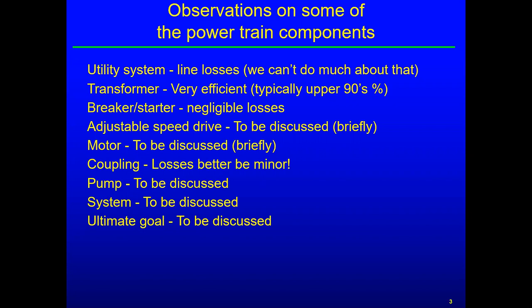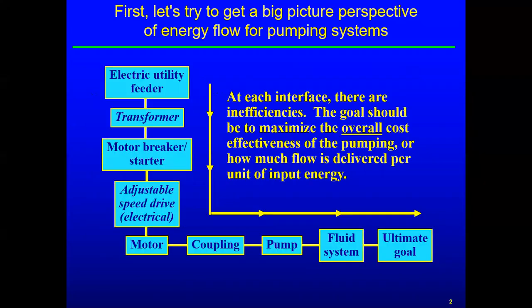The ultimate goal is always important to keep in mind. You sit back and ask: why are we running this pumping system? What is the job? Is it a condenser water pump on a chiller? How much heat do we have to reject, how much should we be pumping, what's a reasonable head? You can do a common sense analysis to estimate roughly what it should cost, then measure the motor and compare. If those two things don't match up, something is going on.